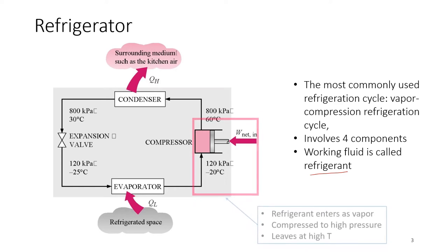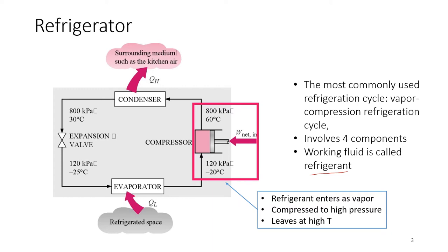Let's start at the compressor. You've learned about compressors in chapter 5 — the compressor needs electricity to operate, it needs power. So we have work input. You have to supply some electricity for it to start working. What it does is it compresses the substance to higher pressure and higher temperature. The refrigerant enters at 120 kPa and minus 20 degrees Celsius in vapor state, and it is compressed in the compressor to 800 kPa and 60 degrees.